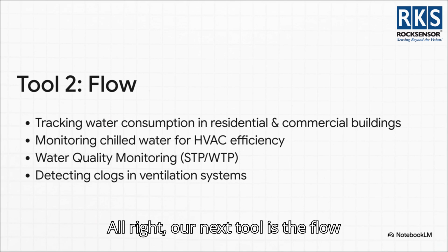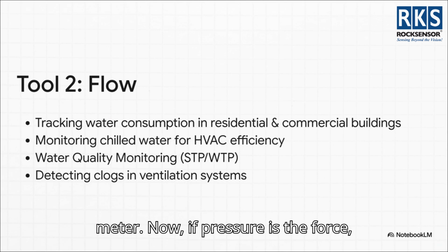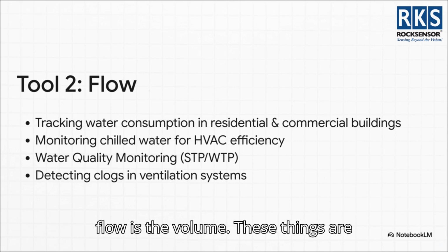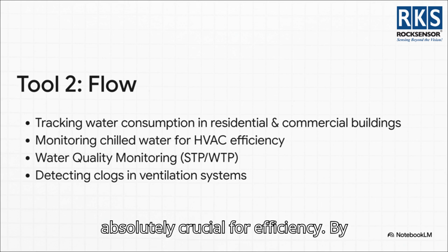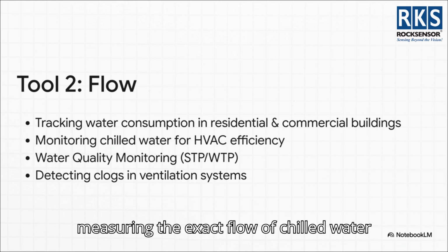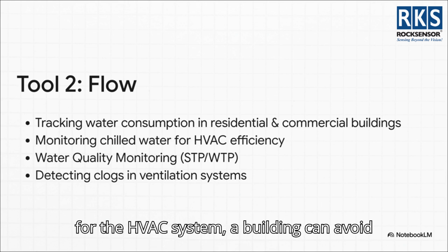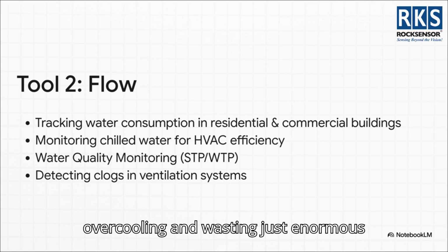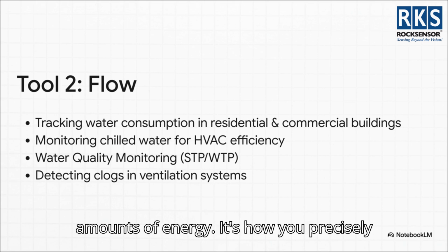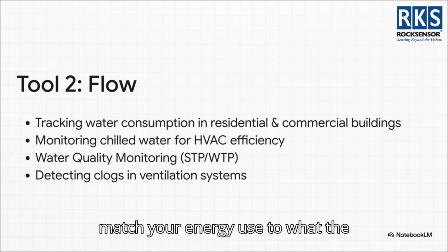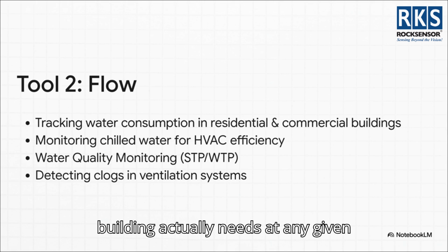All right, our next tool is the flow meter. Now, if pressure is the force, flow is the volume. These things are absolutely crucial for efficiency. By measuring the exact flow of chilled water for the HVAC system, a building can avoid overcooling and wasting enormous amounts of energy. It's how you precisely match your energy use to what the building actually needs at any given moment.